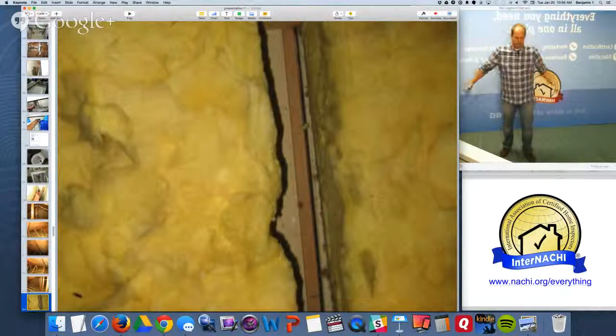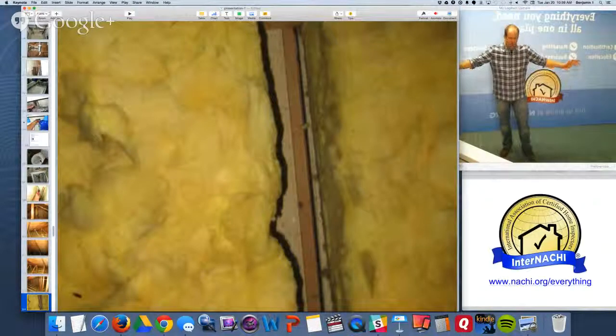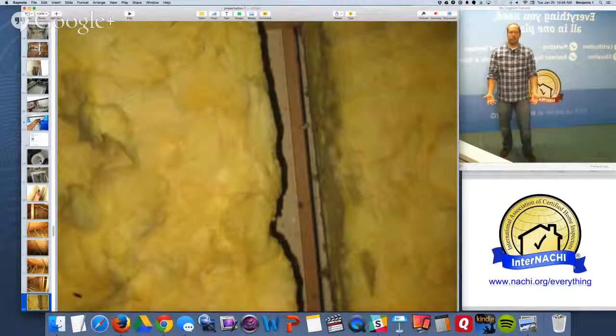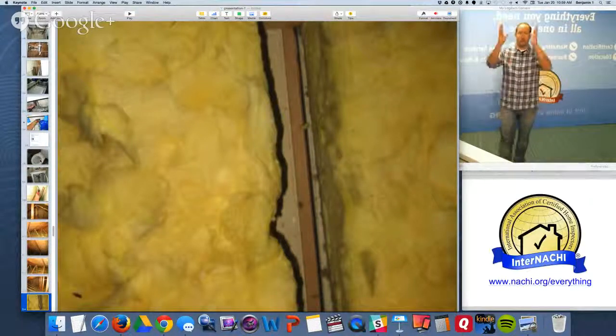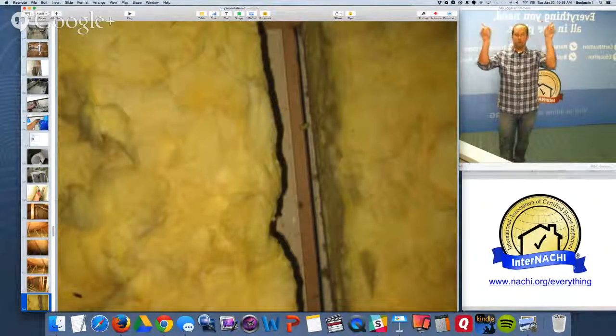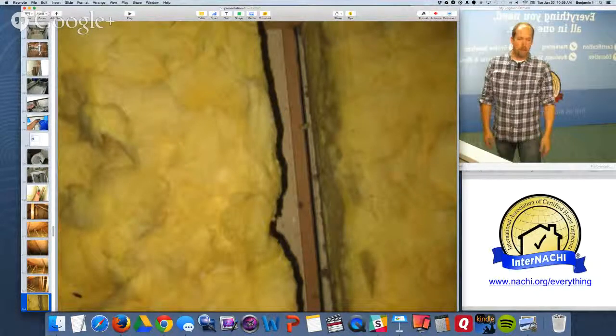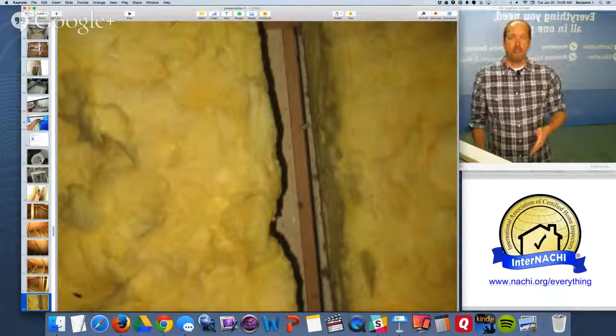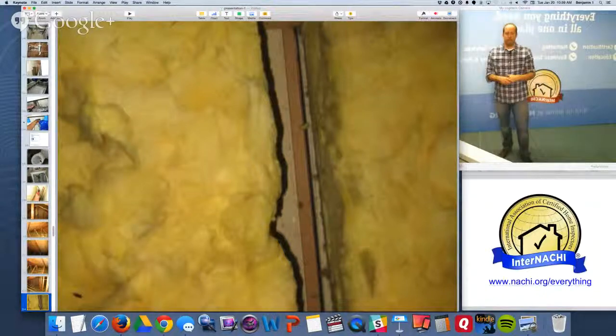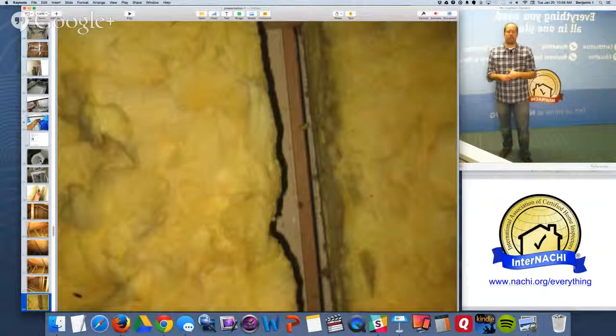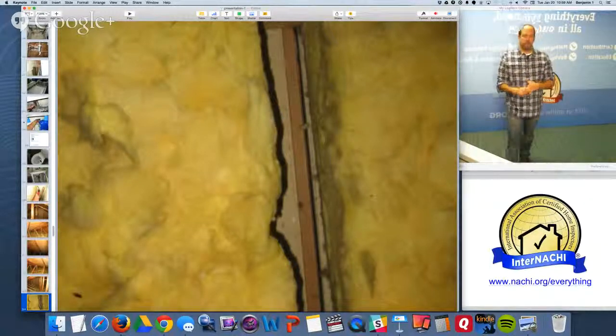There's a natural house stack effect where air is sucked in at the lower parts of the house that are not sealed and moves up naturally and escapes outward on the second floor, third floor, and attic space, carrying dirty air with it. Fiberglass does not stop air — it filters it. We call it filter glass. Here we have open gaps in the insulation, and you can see the dirt on the sides of the fiberglass from the dirty air — it's not mold.